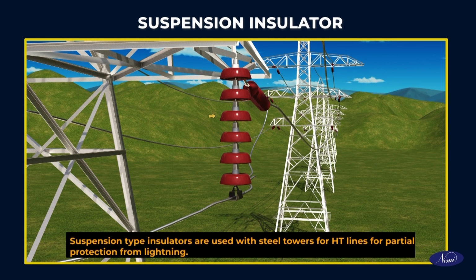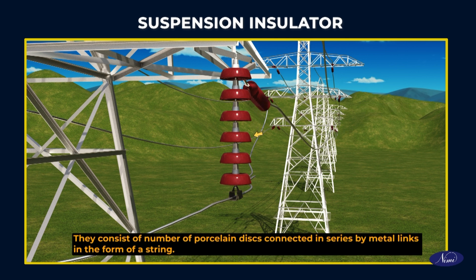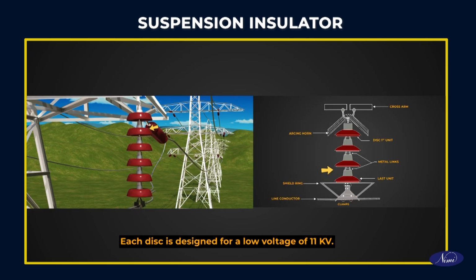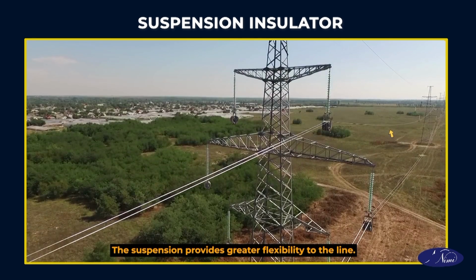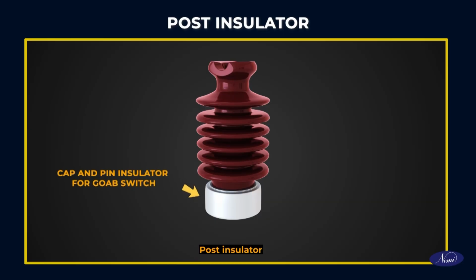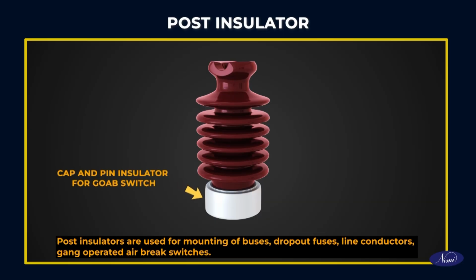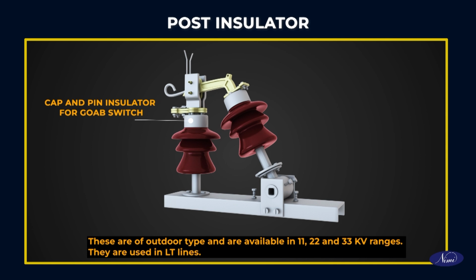Suspension insulator. Suspension type insulators are used with steel towers for HT lines for partial protection from lightning. They consist of a number of porcelain discs connected in series by metal links in the form of a string. Each disc is designed for a low voltage of 11 kV. The suspension provides greater flexibility to the line. Post insulator. Post insulators are used for mounting of buses, dropout fuses, line conductors, gang-operated air break switches. These are of outdoor type and are available in 11, 22 and 33 kV ranges. They are used in LT lines.